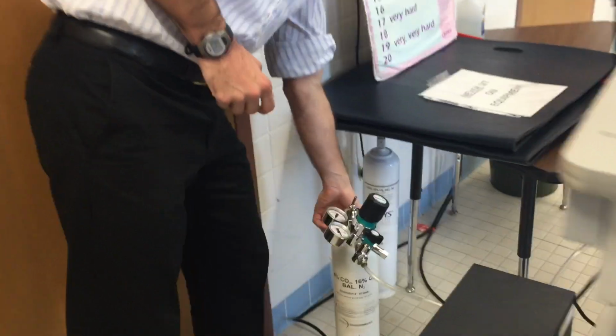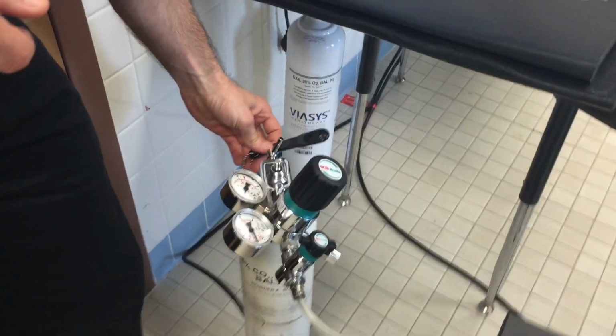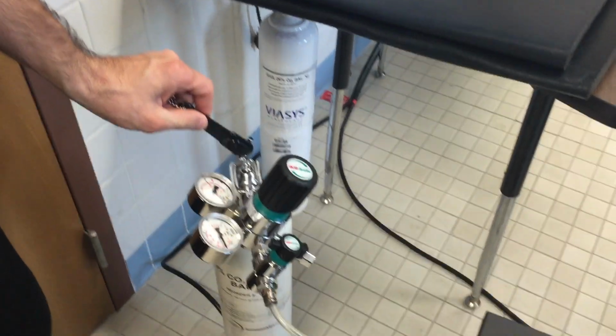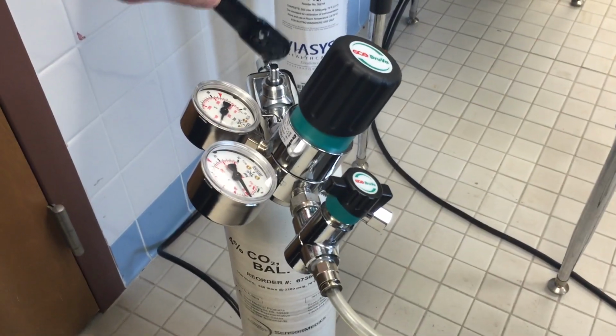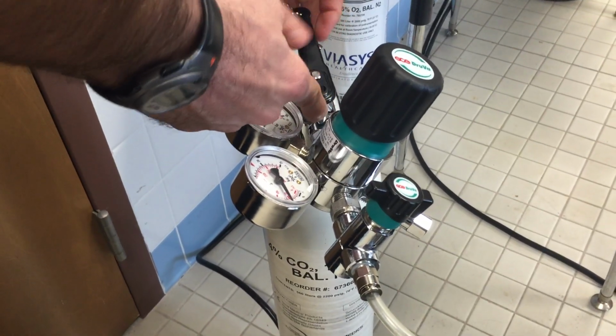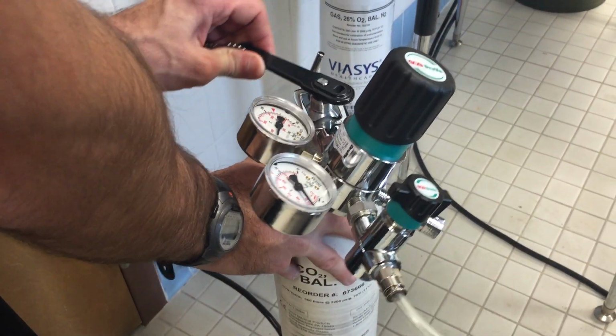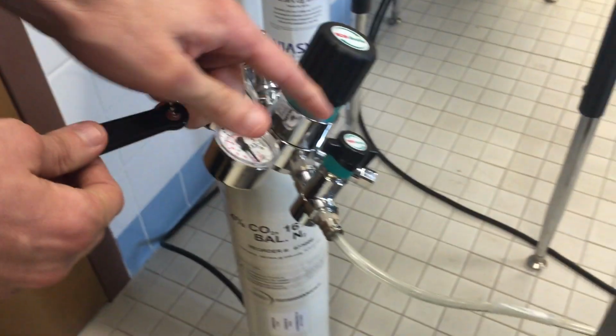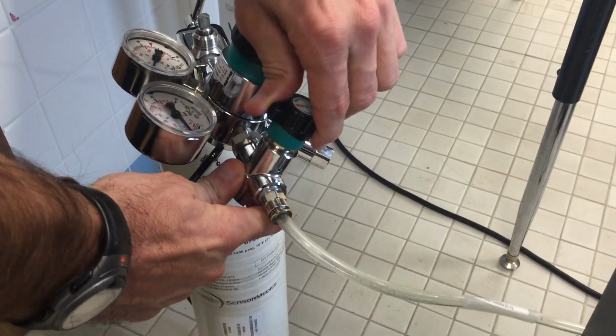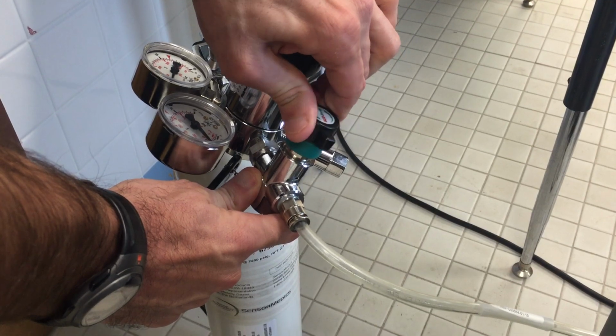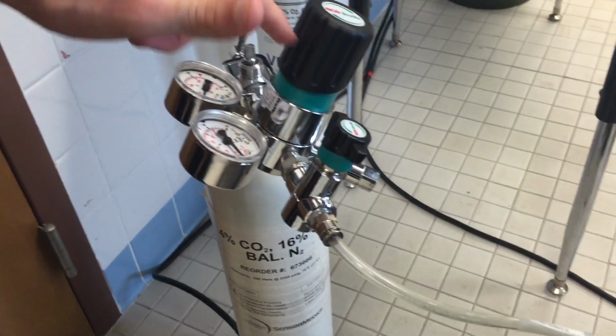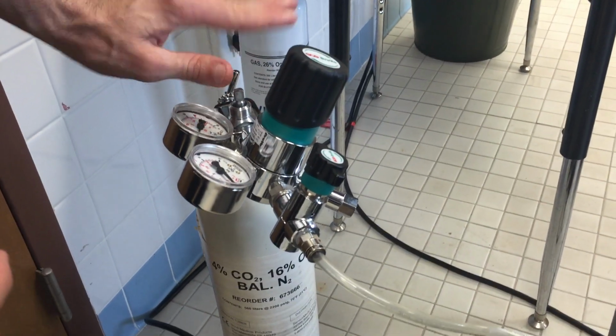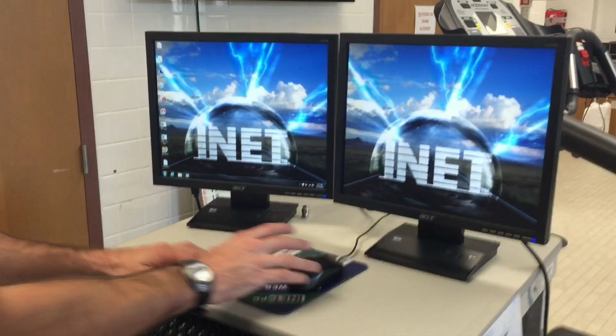After we've turned on our unit and it's warmed up for 30 minutes, we can turn on our gas. We see right over here, we have our tool, which is sitting right on our gas tank. We see two nozzles. We see a little silver one right here, and we see the black one right here. The first thing we do is we turn on this nozzle. We just take our wrench and we turn a quarter turn counterclockwise, just like that. Then we turn this knob again a quarter turn counterclockwise, and if we listen, we hear a click. So once these two are on, this knob and then this knob, we take our tool, we put it right back on our tank so we don't lose it, we know where it is later, and then we have to turn our gas on.